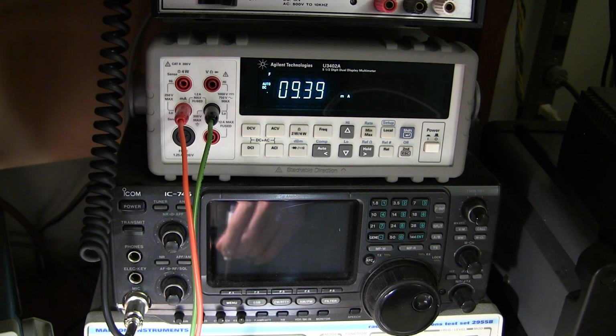We're starting out at about 9.3 milliamps. I'll turn this up and it'll move up quite quickly - we need to adjust this to 500 milliamps. Now this will move around a little bit, so you can keep it keyed for a moment and then adjust it back down. It's very touchy right around the 500 milliamp mark. Don't get too particular over whether it's 499 or 501, that's absolutely fine. I've got it at 499, and if I breathe on it, it will probably move. So there we have it.